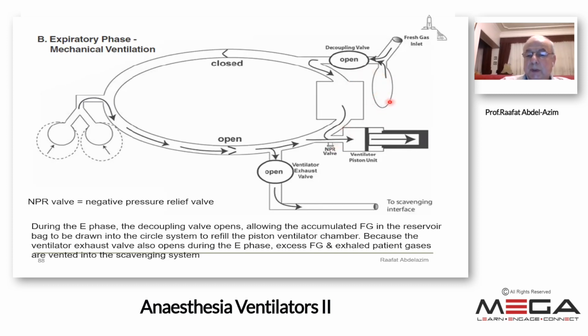If the flow is too low, on moving the piston with negative pressure to take the patient's gas, if all the patient's gas comes out and this one is completely collapsed, there is negative pressure here. If the piston is still moving during expiration, negative pressure will be applied to the patient's lung, causing negative pressure pulmonary edema. To prevent this, the manufacturer has introduced a negative pressure release valve here to let air in from outside, preventing negative pressure on the patient's lung. So this negative pressure relief valve is a safety measure to guard against development of negative pressure pulmonary edema.